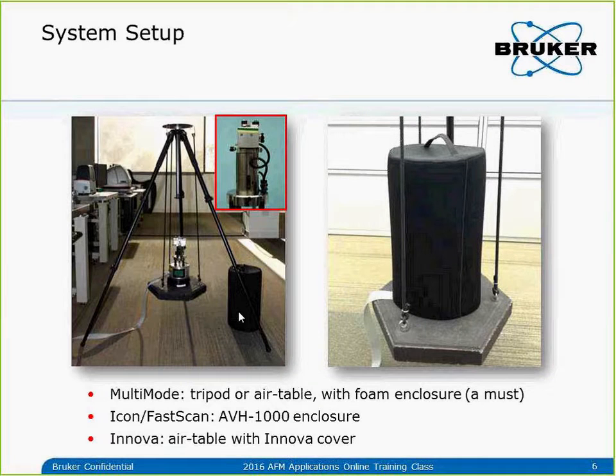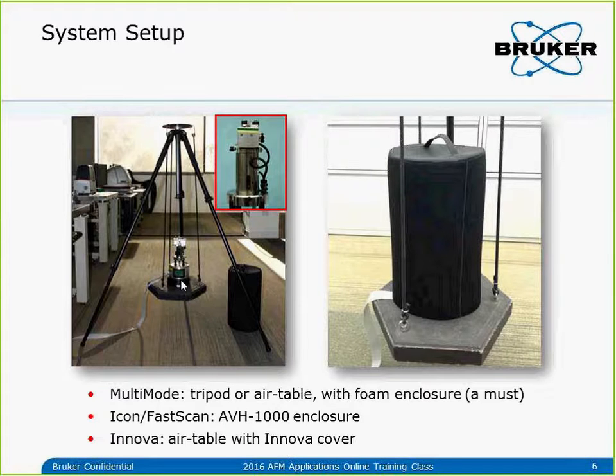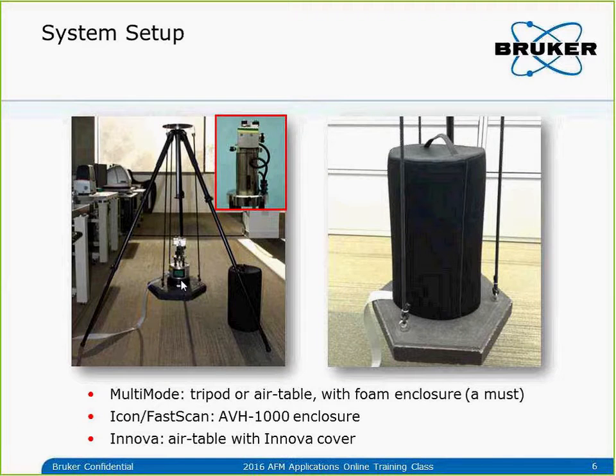Acoustic noise will show up in the image if not isolated properly. If you have a good environment — relatively quiet with a solid floor — the air table is typically sufficient for the multimode. For the ICON and FastScan, the AVH-1000 vibration isolation that comes with the system is typically good enough if the lab environment is relatively quiet. For the Innova with the air table and acoustic enclosure, it's also sufficient to get atomic resolution images.